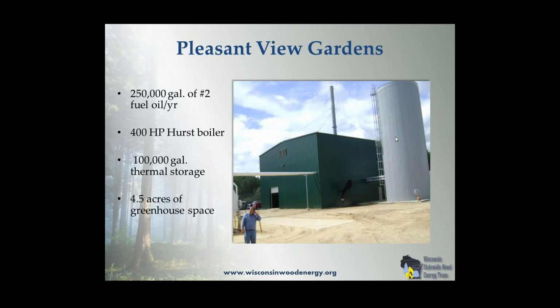Pleasant View Gardens, you can see this big thermal storage tank here. Nobody knows better about thermal storage than greenhouses, and the reason is that you could have a day like today here in Crawford County where the sun is shining and it's 30 degrees and you need to ventilate your greenhouses. The sun goes behind a cloud and all of a sudden you're going to have a huge demand. So this is a huge 100,000 gallon thermal storage tank, and a 400 horsepower Hurst boiler is sitting in this area.